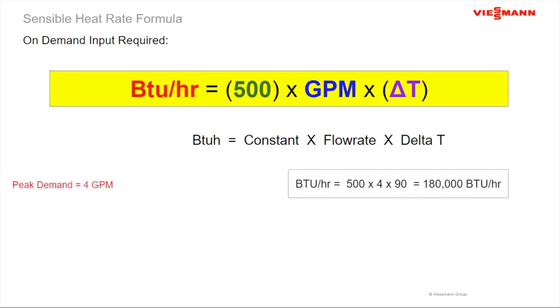So from our earlier discussion, if my peak demand is 4 gallons per minute, I can add my 4 gallons per minute in here. And then I need a delta T. And for our discussion, I'm going to say it's going to be a 90 degree delta T. So if I'm looking at the firing rate needed to produce this hot water on demand, I take my 500, I multiply my 4 gallons per minute, I multiply that by 90, I get 180,000 BTUs per hour. And that becomes the output of the boiler to provide domestic hot water, okay? So all of a sudden, I know what I need from a combi boiler standpoint. I need 180,000 BTU output. And with that 180,000 BTU output, I can get 4 gallons per minute.